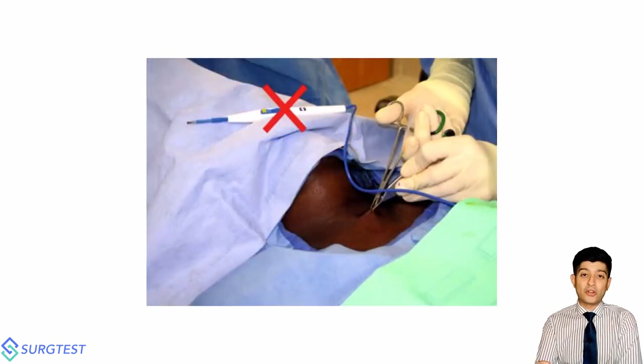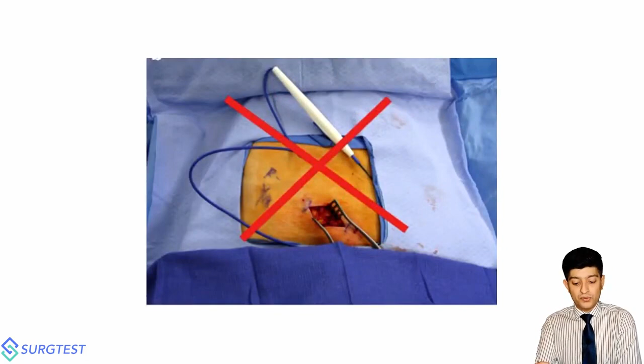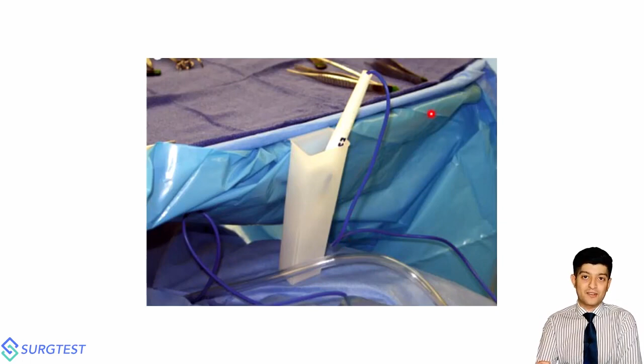But these images are going to tell you what is not supposed to be done in the OR. Please don't keep the cautery pens on the patient body when they're not being used. Most of these pencils come with a plastic non-conductive little basket that once again is not kept on the patient body, mind you. It's actually hung from one of the scrub trays on the side from the sterile trolleys.